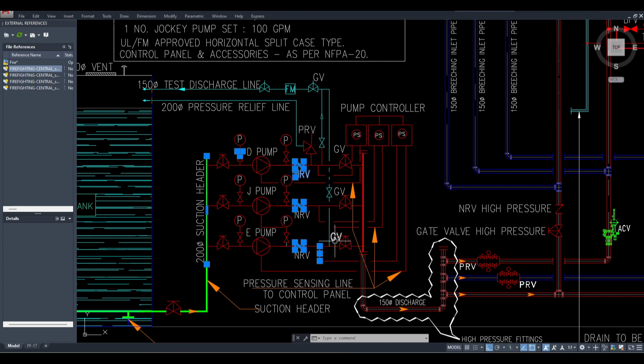Then after modeling, whether they have connected it. Now see, the test line is connected separately for the electrical pump and the diesel pump, sorry, not the jockey pump. These two are compulsory to connect because these are the powerful pumps. The jockey pump is only to maintain the pressure, so there is no big GPM requirement there, but these pumps have to have a GPM requirement. I will explain GPM later in the design stages.